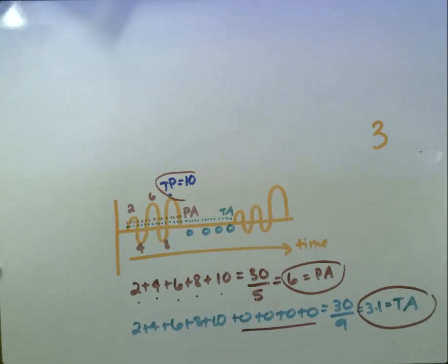That all makes sense. But the question or the commandment that we were talking about basically was that if a pulse and a continuous wave have the same SPTP, then the continuous beam should have a higher SPTA. So let's look at what that would mean.